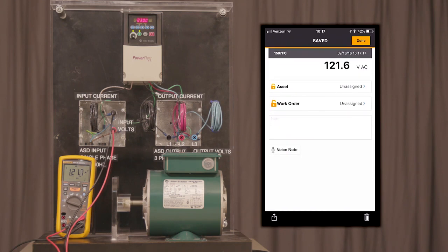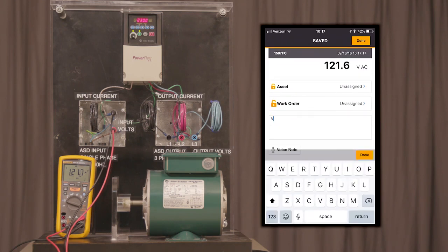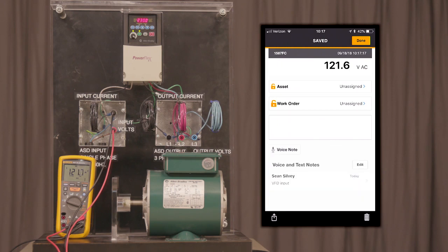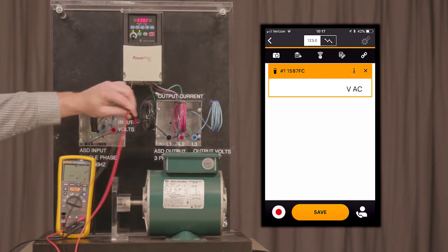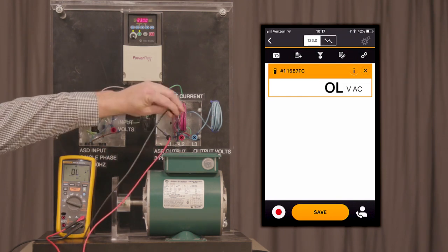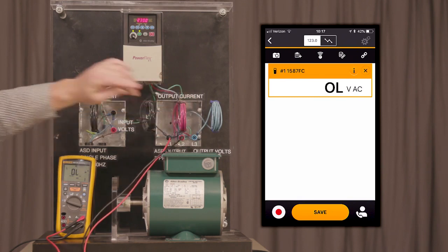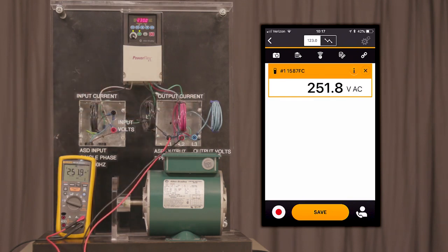We're going to save this measurement into our Fluke Connect app. So now that we've made that measurement and saved it, let's check the voltage of the output of our VFD. In this case, we're going to go from L1 to L2. As you can see here, the output voltage that we're reading is 251.